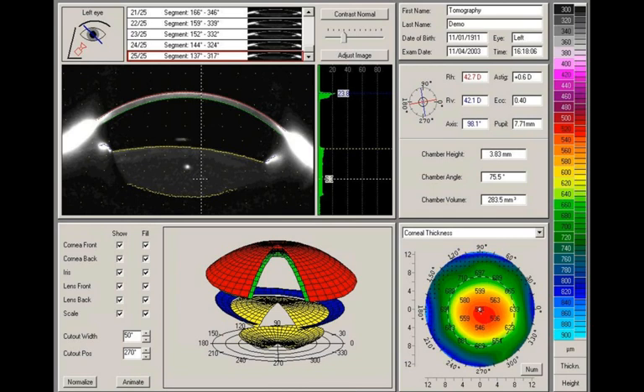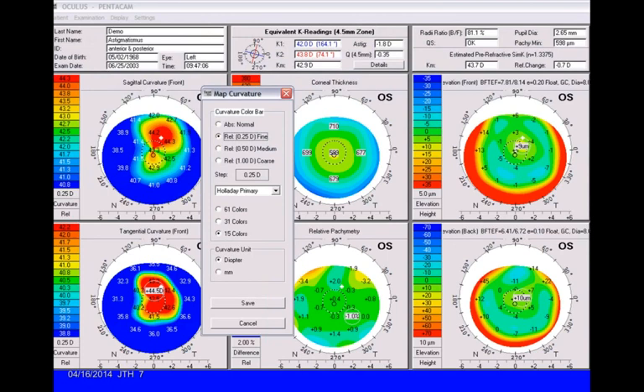Because you can't create a three-dimensional image without an accurate point of registration, the registration here allows us to make a very accurate—within about 10 microns—three-dimensional image of the anterior segment. With this, we're able to generate a report. The doctor sits in a room with a patient and needs a report that's comprehensive, providing all the information necessary to examine and treat the patient. The technician makes the measurement, so the report has to have all of the information you need. We'll have maps on the first page and some details on the second page.